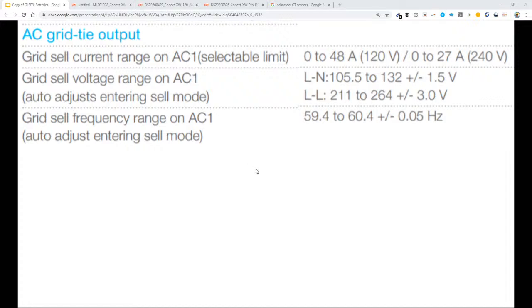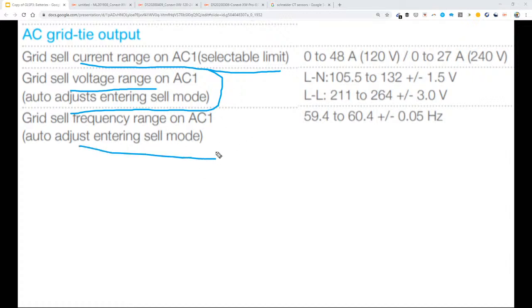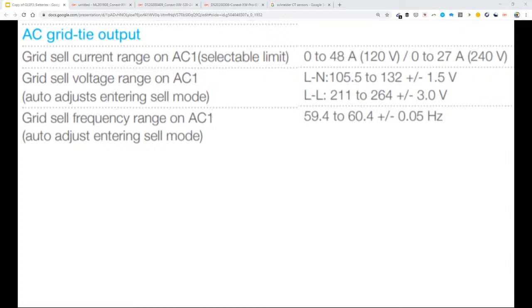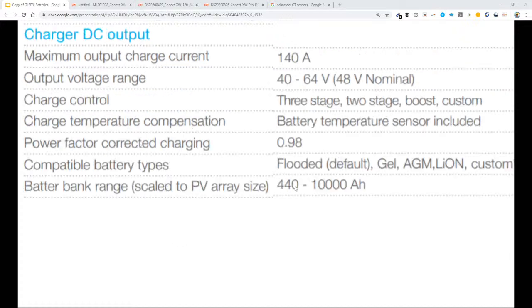Here's the grid tie output range. It says you can input how much current you want to sell back. You can say, okay, with the battery voltage, depending on the grid voltage, you can use the inverter to help stabilize that grid voltage or raise that grid voltage. You can do frequency control. These are advanced features that utilities kind of like.